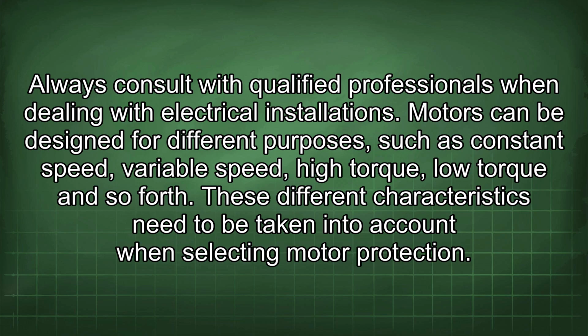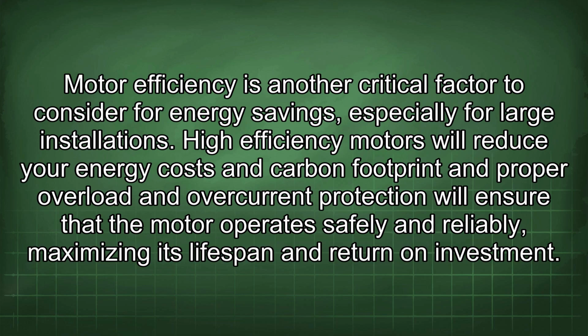Motors can be designed for different purposes, such as constant speed, variable speed, high torque, low torque, and so forth. These different characteristics need to be taken into account when selecting motor protection. Motor efficiency is another critical factor to consider for energy savings, especially for large installations. High-efficiency motors will reduce your energy costs and carbon footprint, and proper overload and overcurrent protection will ensure that the motor operates safely and reliably, maximizing its lifespan and return on investment.